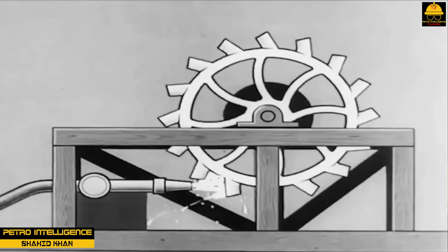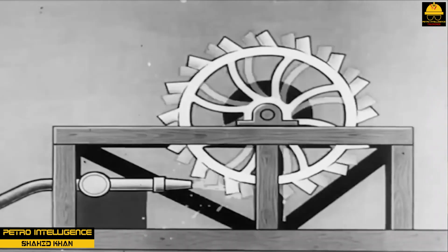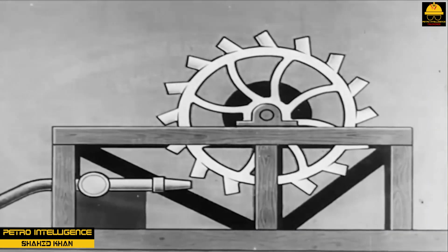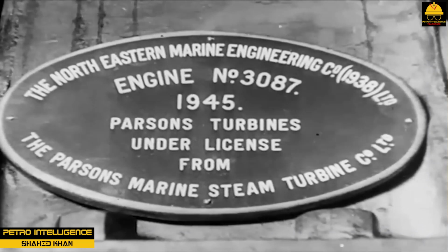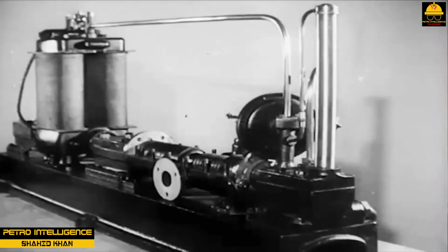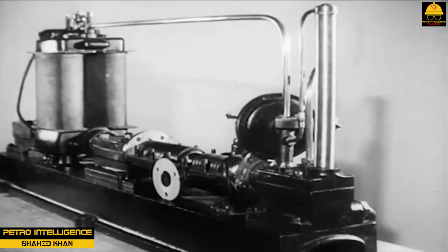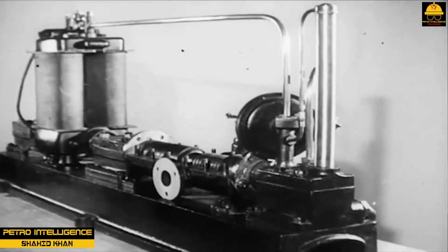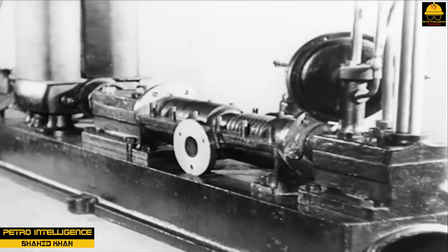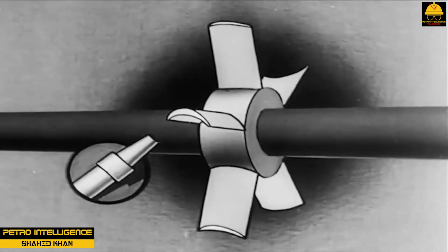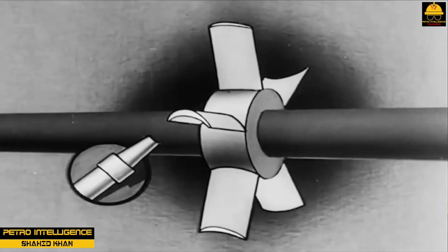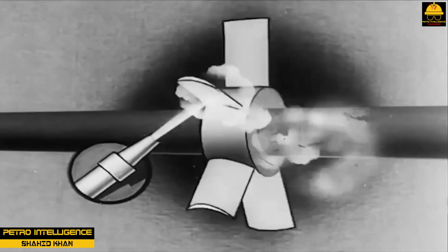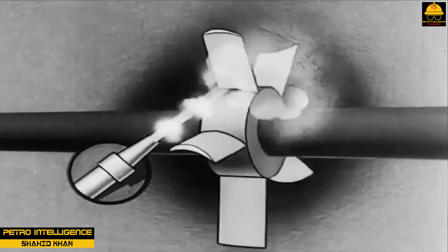Technical improvements to the steam turbine design have enhanced efficiency and power. Steam turbines have replaced the once popular steam engine because they weigh less and occupy less space. Steam turbines operate with little or no vibration because they have little, if any, back and forth motion. Turbines are very efficient when run at high speed under a heavy load. Turbine efficiency drops drastically when the equipment is slowed down.